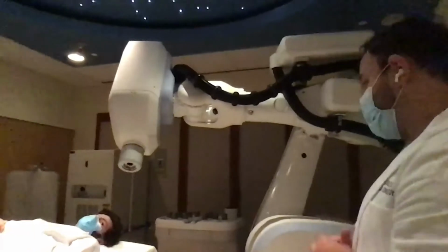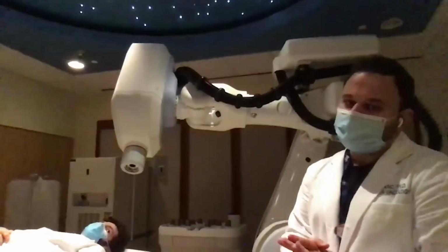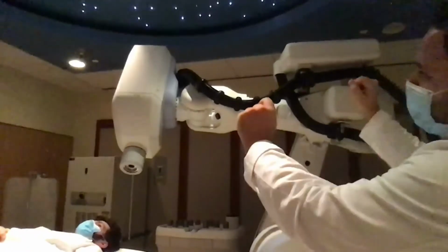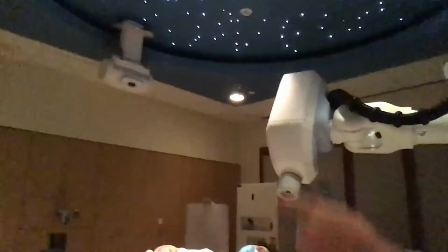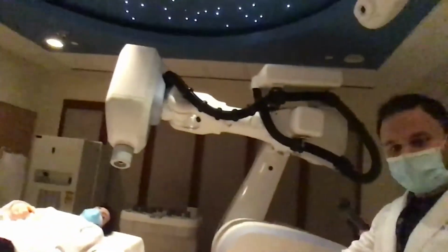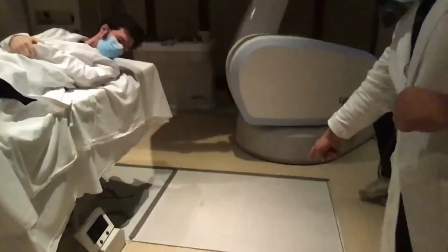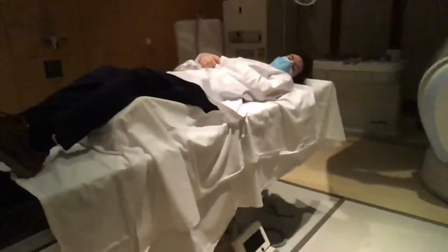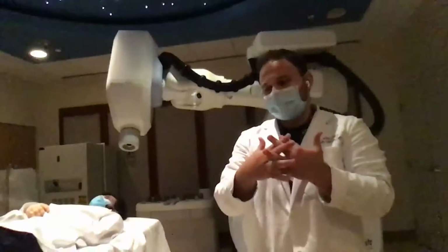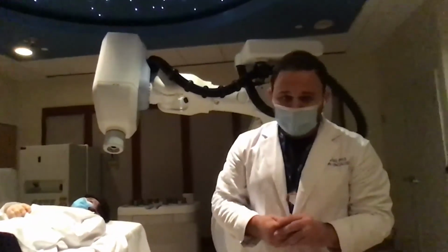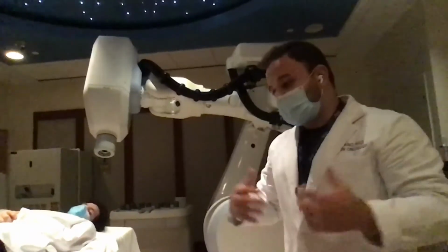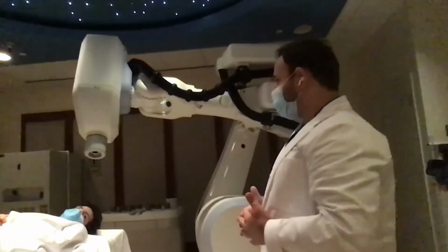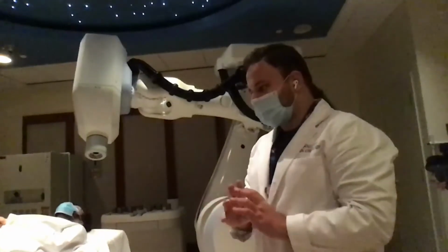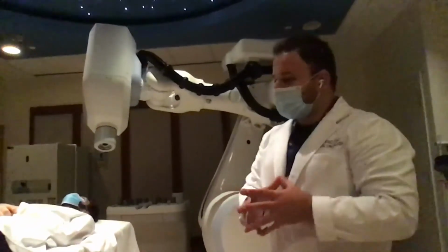During treatment, which could take up to 30 minutes, we also use X-ray imaging. There are 2 X-ray tubes which are located in the ceiling. So there is one X-ray tube and there is another X-ray tube up there. And these X-ray tubes shoot X-rays onto the floor. So there is an X-ray detector on the floor here, and there's another X-ray detector on the other side. And as the patient lays there, X-ray images are acquired periodically, sometimes every 30 seconds or every minute. And these are used to ensure that the patient is in the same position as set up during treatment.